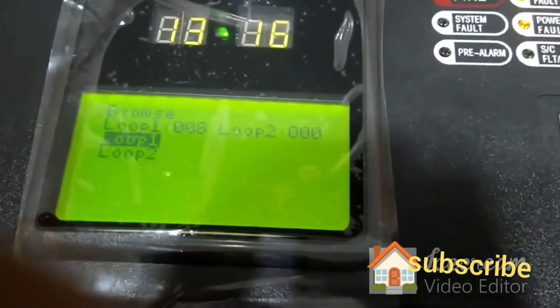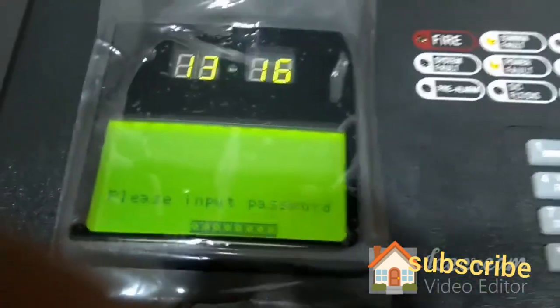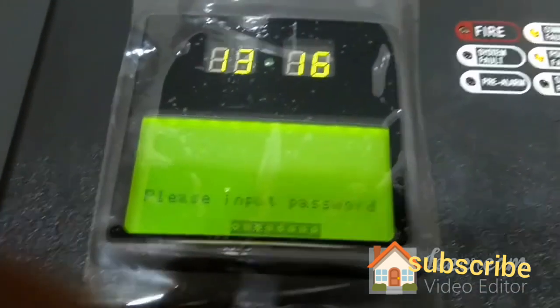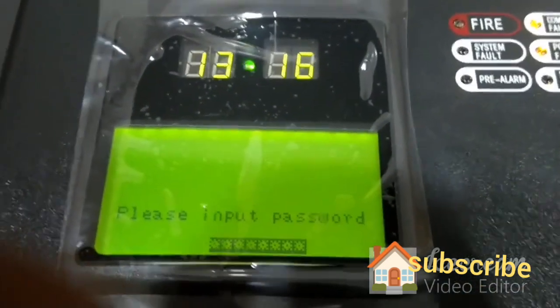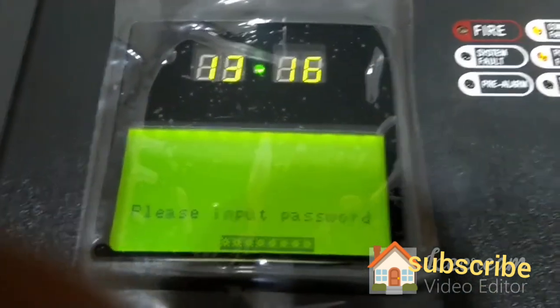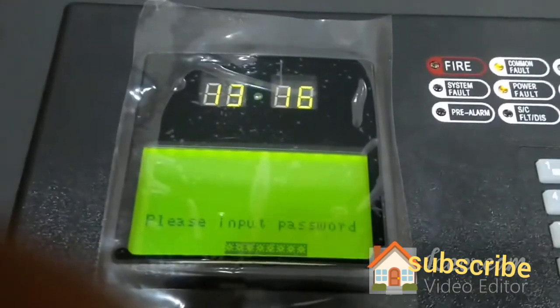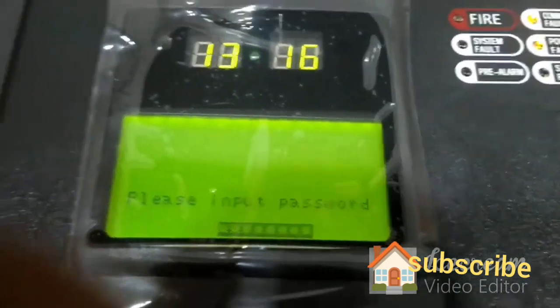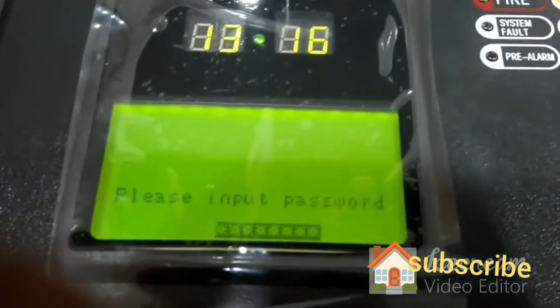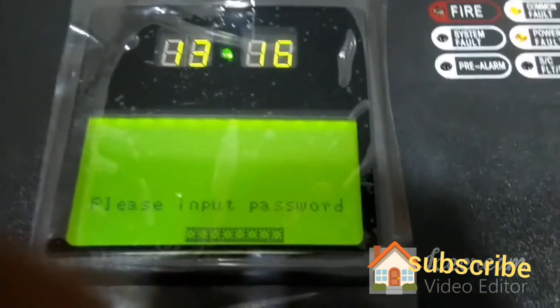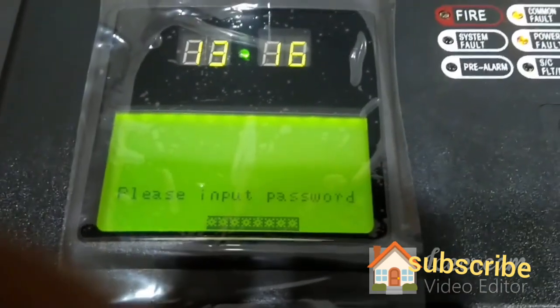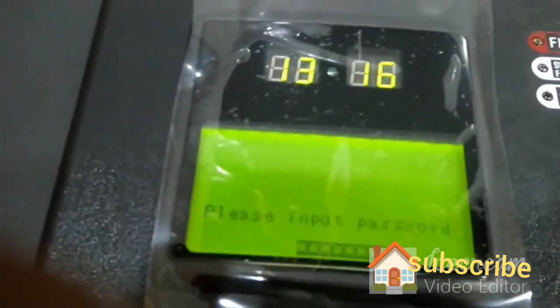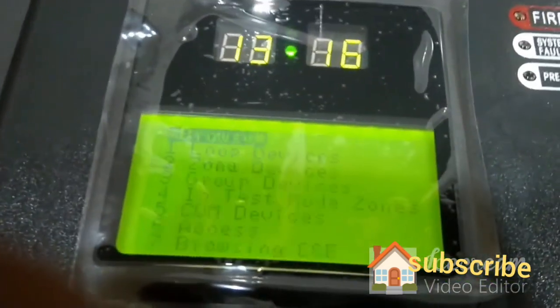Again you need to go to System. It will ask for the password; you need to do the same process. The commissioning password is 24220011. Press Enter, then press and release the SK1 button, so that the panel will do the auto learn process once again. It will take the devices that are newly found, and finally it will give the final number in the Browse page.